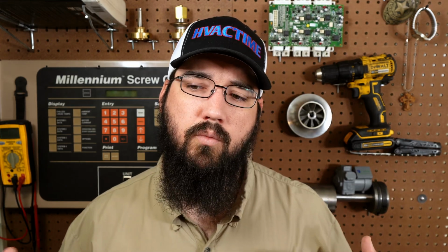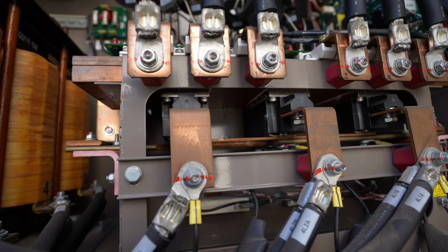So let's start with, where do we use these? There's two main areas that they get used. It's in a soft starter or a VFD or VSD, whatever brand you're working with, AFD if you're dealing with a Trane. Either way, those are the two main applications where you'll come across SCRs in the chiller world. Now, you also see them outside of chillers. Let's say you've got a fan power box or something, they may use them to control the heater, right? We can do variable heat control and so on.